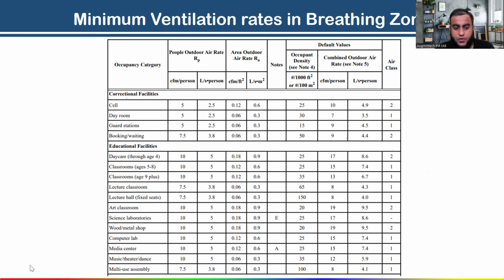See, in the first column the occupancy category is given. Can you see the correctional facilities, educational facilities? Under this educational facility, the classroom age 9+ is given. All of you can view this. For classroom age 9+, what CFM per person value do we have to consider? 10, and CFM per square feet 0.12. To find out the occupant density, number of people, it is given for 1000 square feet. For every 1000 square feet, how many people maximum can you consider?